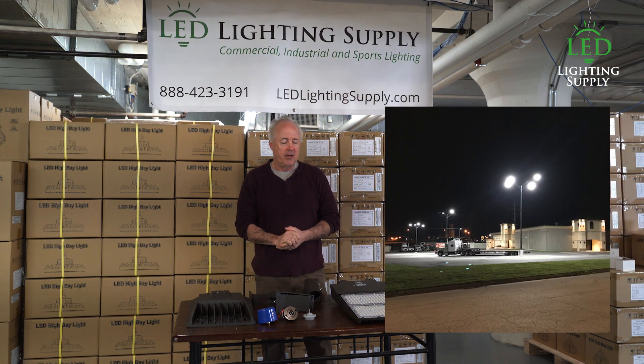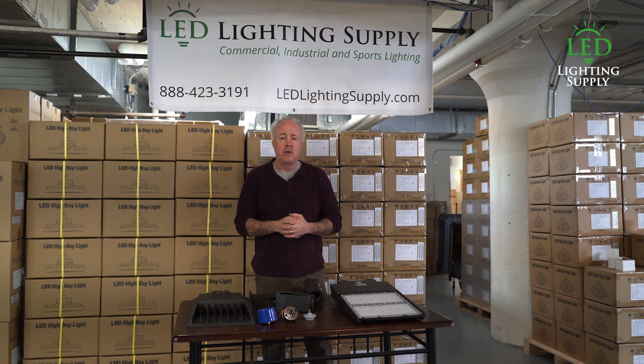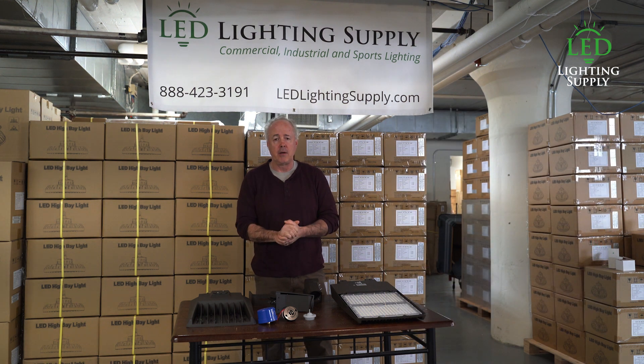You want pretty uniform lighting. In a standard business parking lot, you really don't need a lot of light — one to two foot candles is all you need. When you move into a retail location, you want to get north of 10 foot candles if possible. In car dealerships, you even want more because you want the facility to pop.